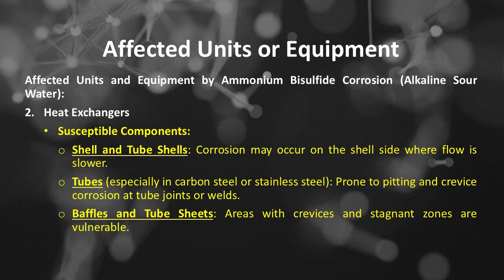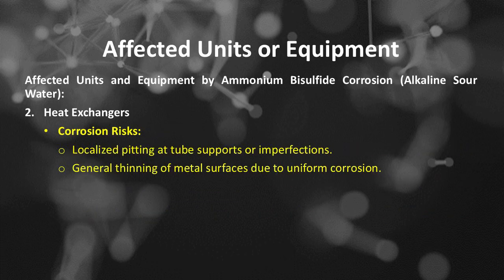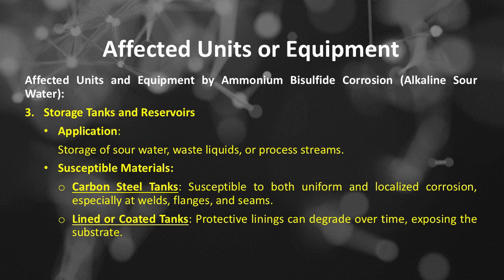Tubes, especially in carbon steel or stainless steel, are prone to pitting and crevice corrosion at tube joints or welds. Baffles and tube sheets, areas with crevices and stagnant zones, are vulnerable. The corrosion risks of heat exchangers include localized pitting at tube supports or imperfections, and general thinning of metal surfaces due to uniform corrosion. Affected units and equipment by ammonium bisulfide corrosion or alkaline sour water.